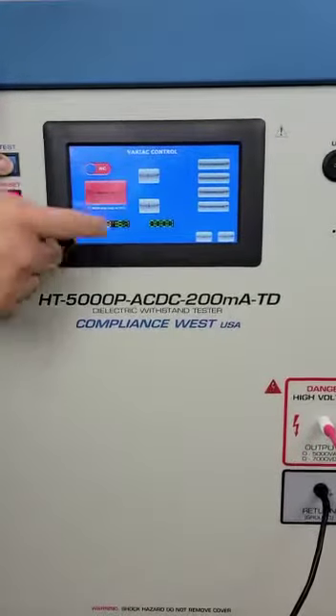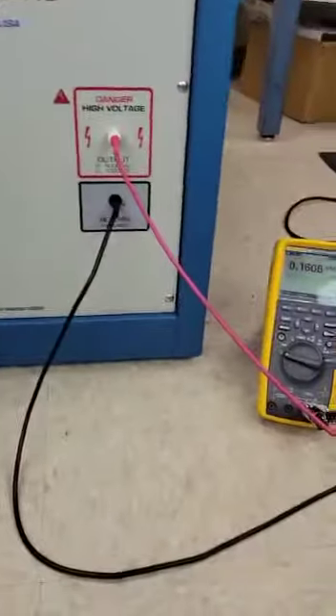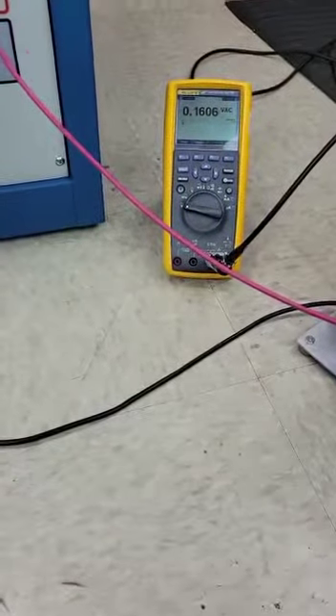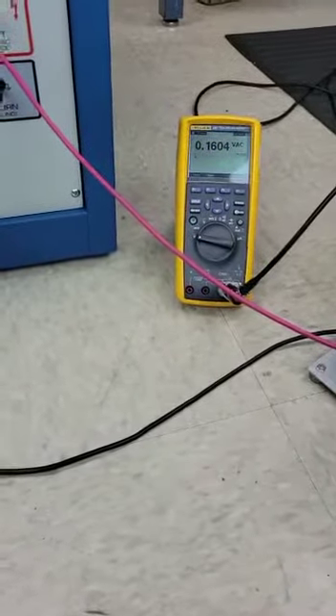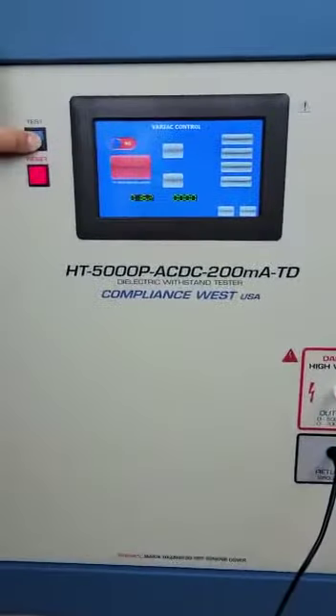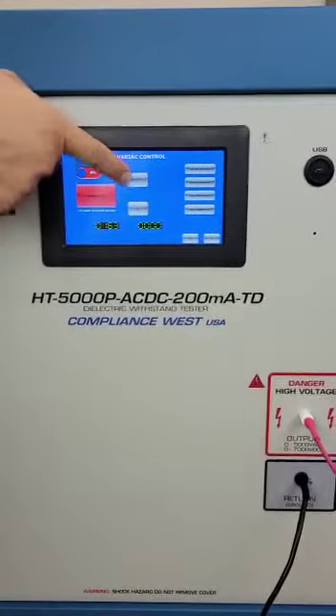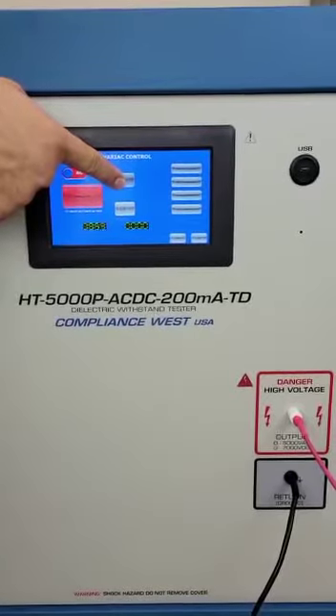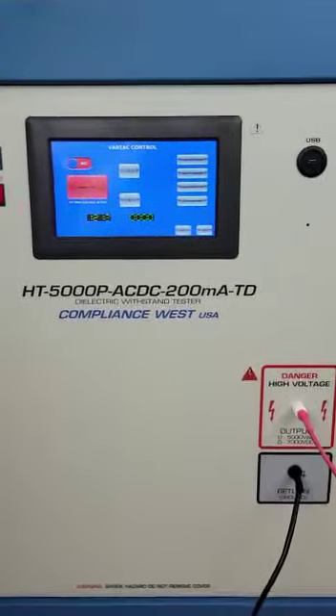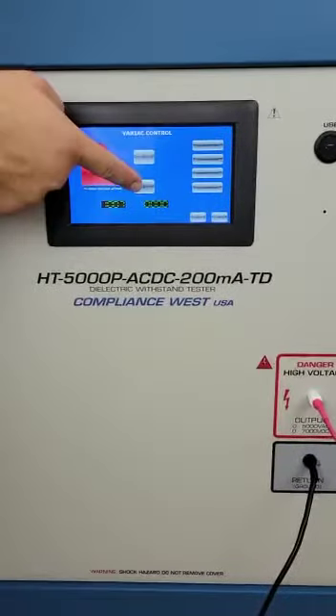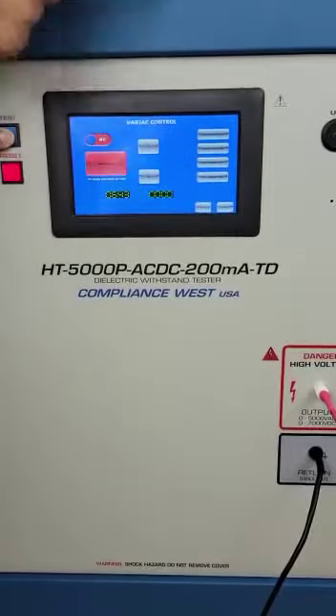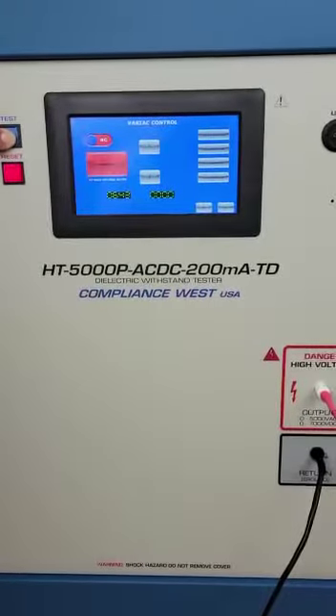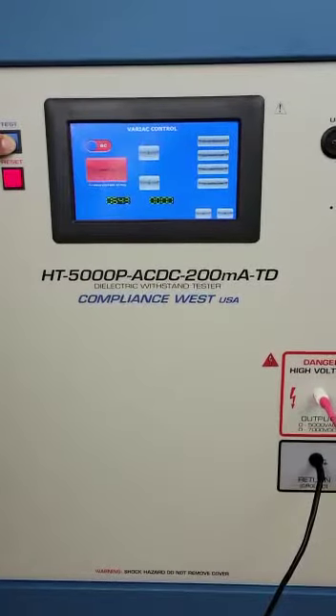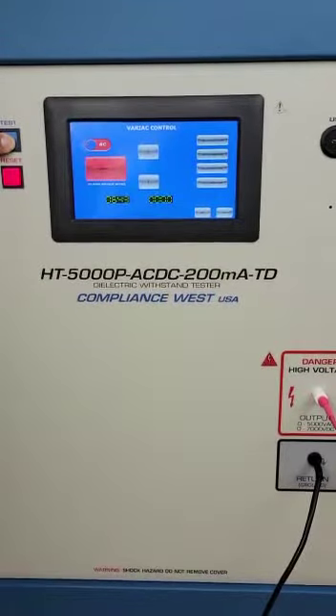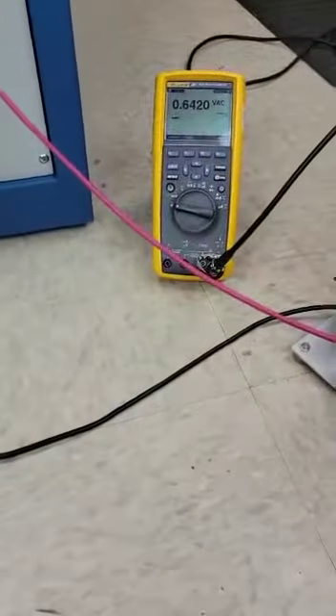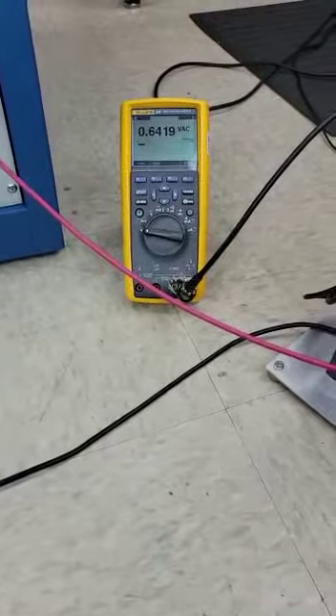Voltage is enabled, and we can see on the meter that we start reading voltage, 160 volts. Remember those 1000 to 1. We can increase by pressing the up. To calibrate the low voltage, we recommend calibrating at a voltage of around 600. You can select any voltage, but 600 is a good starting point, or something close. Once you are there, you can just make note of the value that you have on the meter, 642.